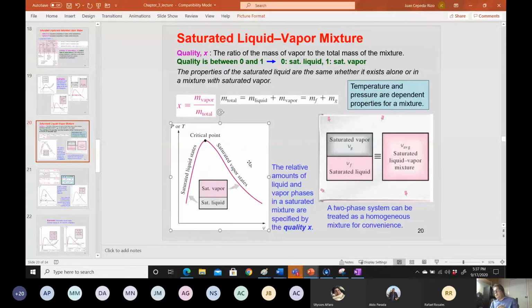So it means that that liquid has a temperature, which is defined by the boiling temperature. For atmospheric pressure at sea level, it's 100 degrees Celsius, and thereby you also know the pressure, because water boils at sea level at 100 degrees. So that sea level pressure is 14.69 psi or 101.3 kPa. So by knowing T, you know P, and by knowing P, you know T for saturated steam or water, for any saturated liquid.